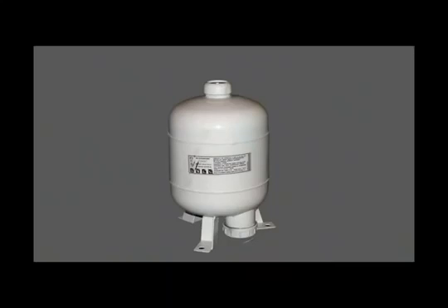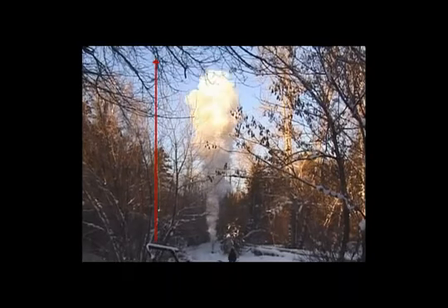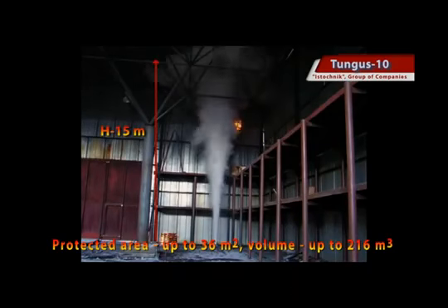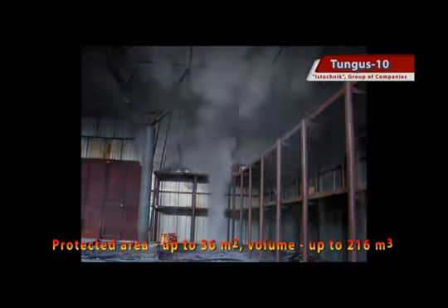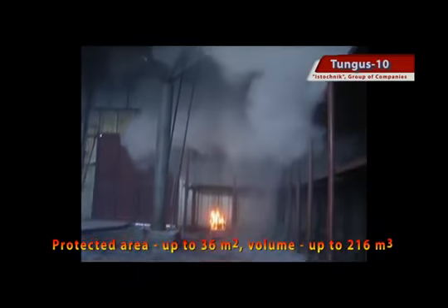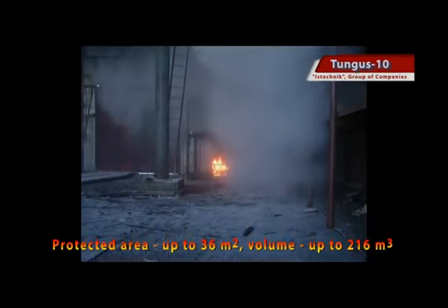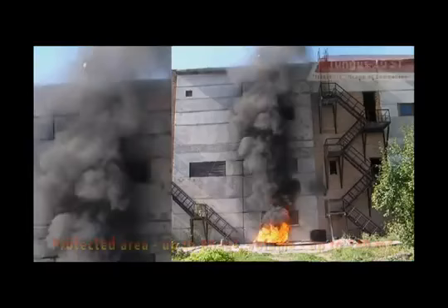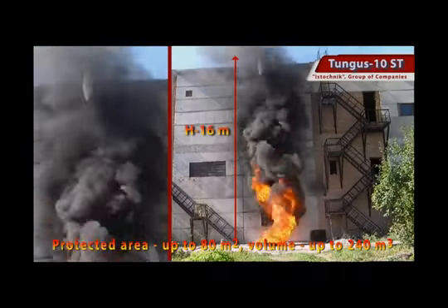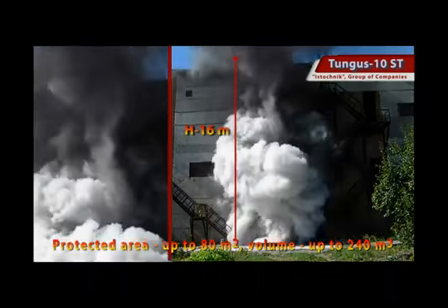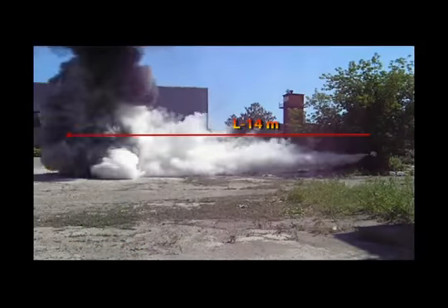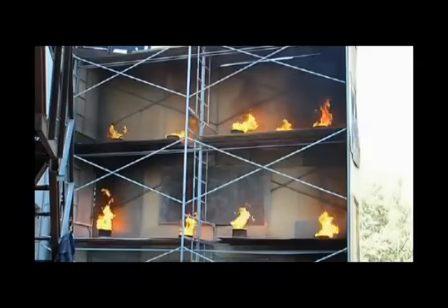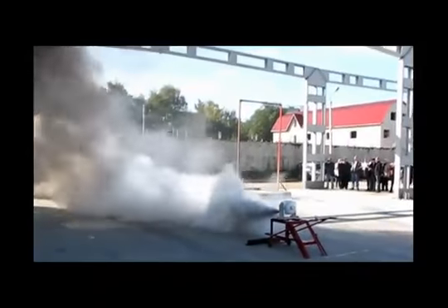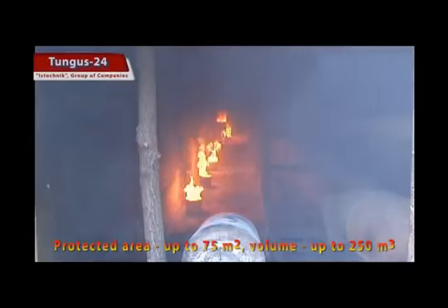The modules provide firefighting powder emission in any direction, so it makes possible to avoid forming of shaded areas and to provide reliable fire extinguishing of objects of any configuration and extent. During the usage of various modifications of the modules, fire defense of objects of almost all purpose and geometry is provided. The range of objects is from electrical cabinets with a volume less than 1 cubic meter to storage houses with a volume of hundreds of cubic meters and with height up to 16 meters.